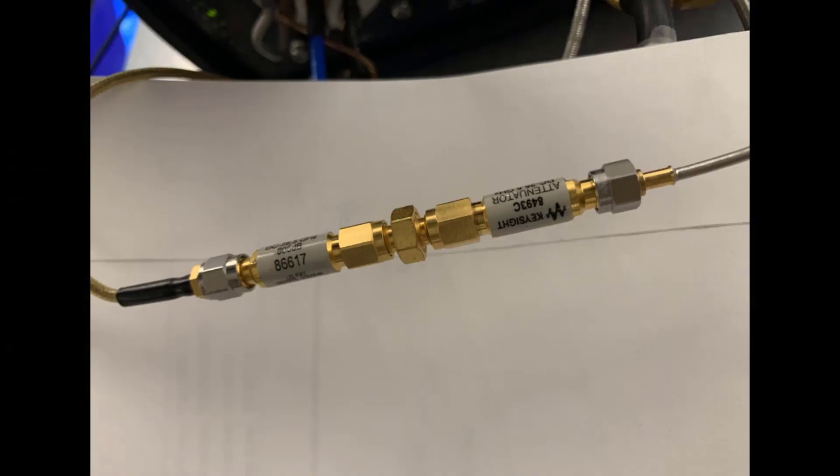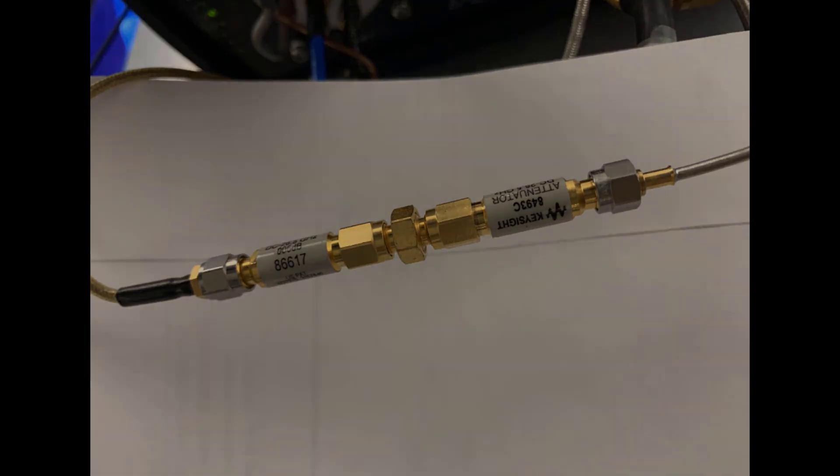Let me note that I did the calibration step with a small through adapter in line with two attenuators. I put one attenuator at the end of the cable from the VXG and another attenuator, a 60dB attenuator on the cable going from the device interface to the UXA. That's because we can't do mismatch correction with this, and the filter has not great match, and so we'll get mismatch ripple if I don't have a really good matched response, and this removes or reduces the effect of mismatch in the cable and the VXG source, and in the cable going to the UXA receiver.